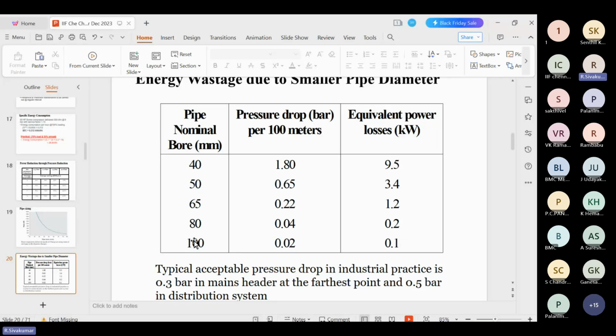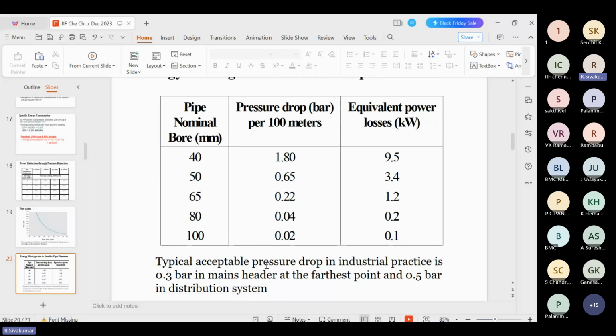So a 100 mm bore size means the energy loss is 0.1 kilowatt and the pressure drop is 0.02. The typical acceptable pressure drop in industrial practice is 0.2 to 0.3 bar on the generation side, and at the tail point, the farthest point of the industry, it is 0.5 bar. That means you have 3 or 4 compressors in the compressor generation system. There is a final air dryer and a receiver. You can see the output of the air dryer and the air receiver.